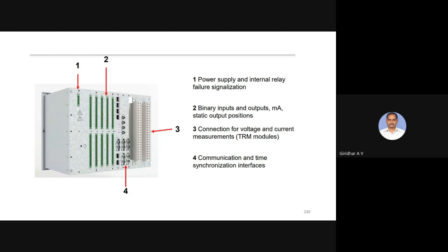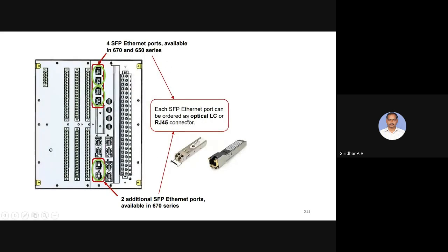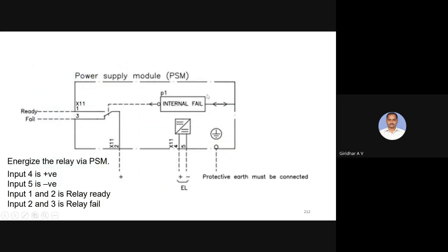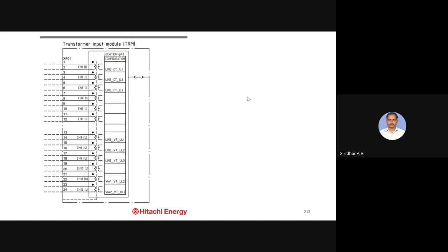So these are the power supplies. Even if there is any problem with one particular IED, it can be communicated to other IEDs also. Those features will be there. In that way, communication is effectively passed to the master station about the particular IED where some problem occurred, and it will also be passed to the other IEDs. Some features will be added into that.